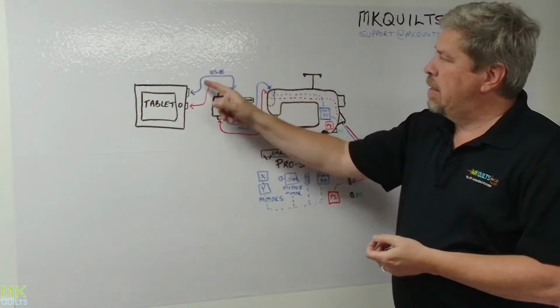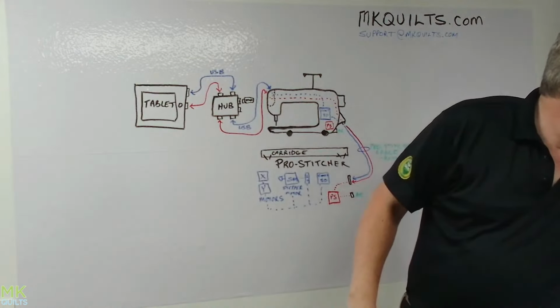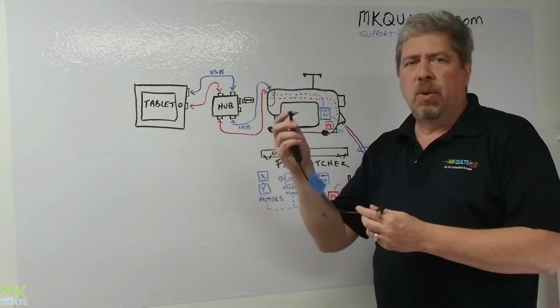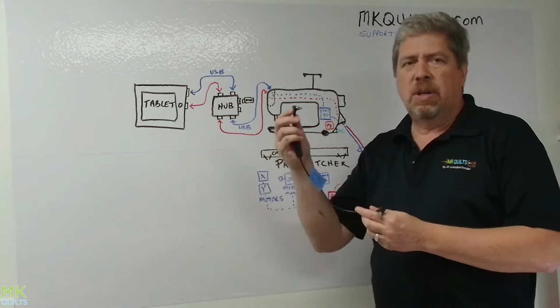So what we ran into with this cable was that somehow this got loose. Somehow this cable plugged into the tablet, I could just wiggle it a little bit and get that noise of it losing communications with the machine. The only way I could be 100% sure that I'd solved the problem was to try swapping the cable with a new cable and then wiggle it again to see if the problem went away.